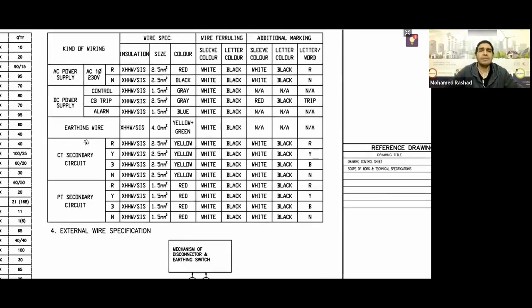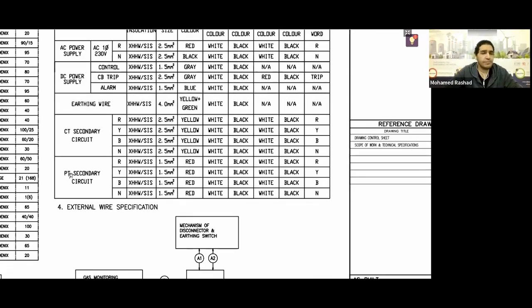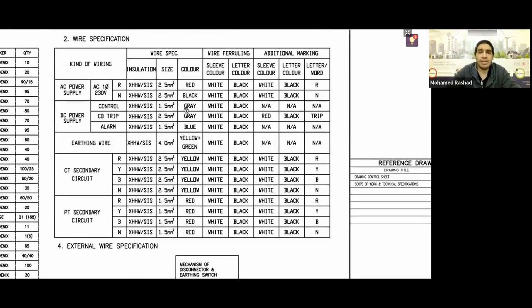Regarding the CT and VT circuits, you have red, yellow, blue, and neutral. All CT circuits must be 2.5 millimeters internally. All VT circuits are 1.5 millimeters. All CT circuits have their wire color as yellow, and all VT circuits have their color as red. The ferrule on it is white with black writing, and there's additional tagging like a number that says RYBN, RYBN, standing for red, yellow, blue, neutral, red, yellow, blue, neutral.